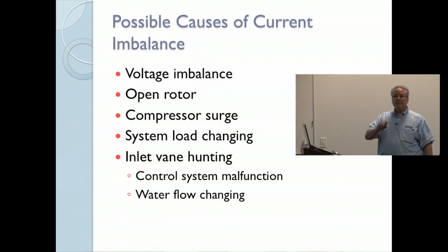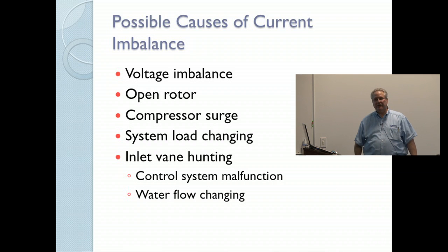System load changing, you may have controls or a system that's constantly hunting, and that can cause some imbalances once in a while, which I guess is the same thing as inlet vane hunting, which could suggest a control system malfunction or water flow that is changing dramatically.